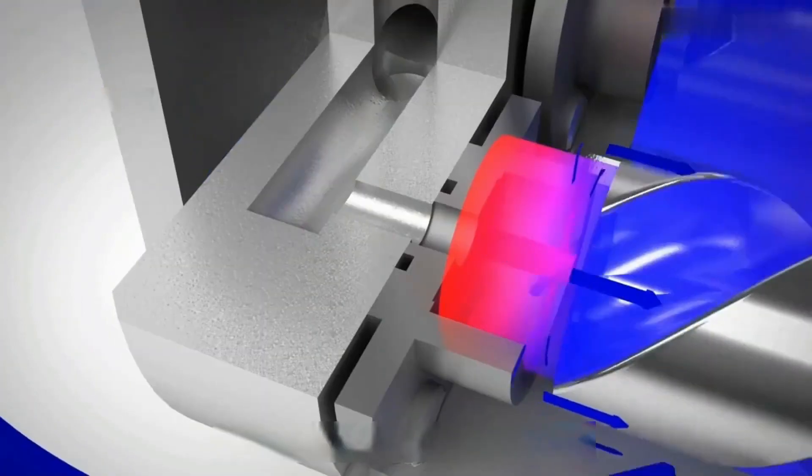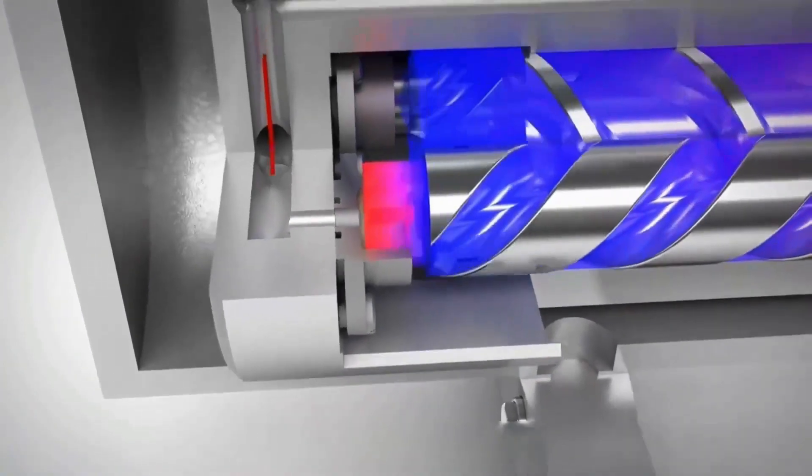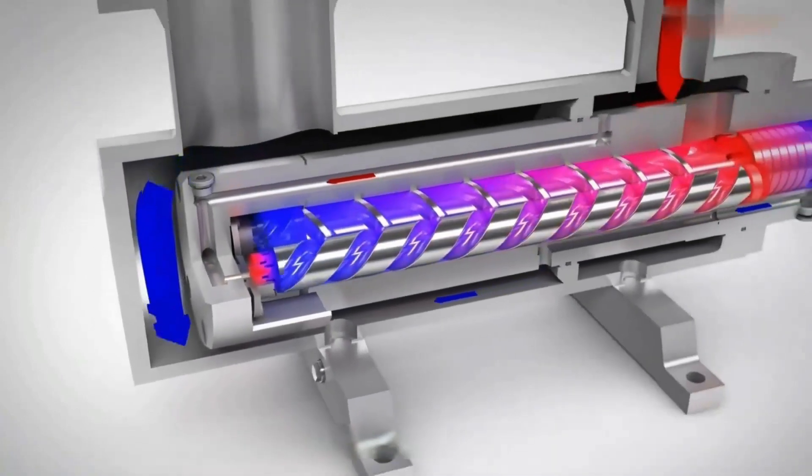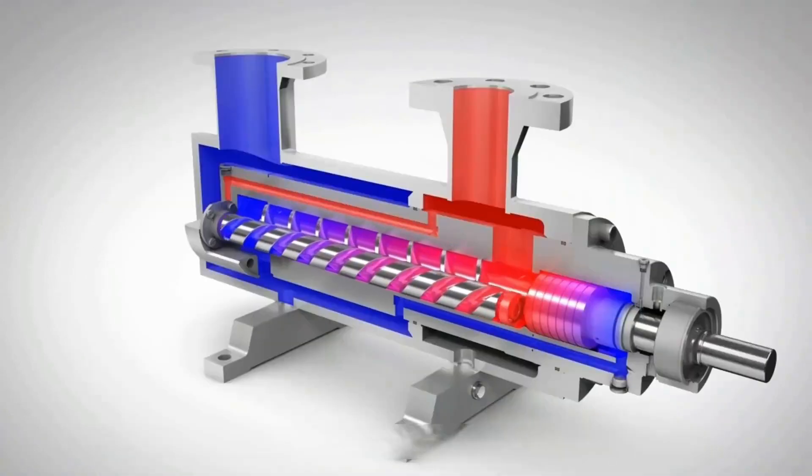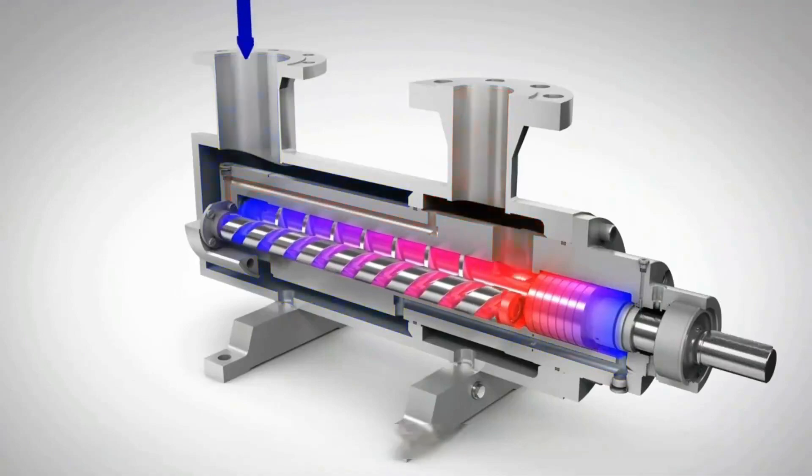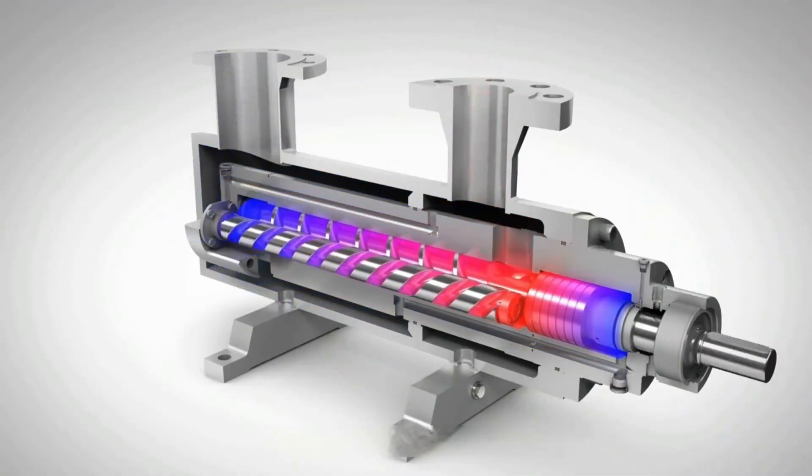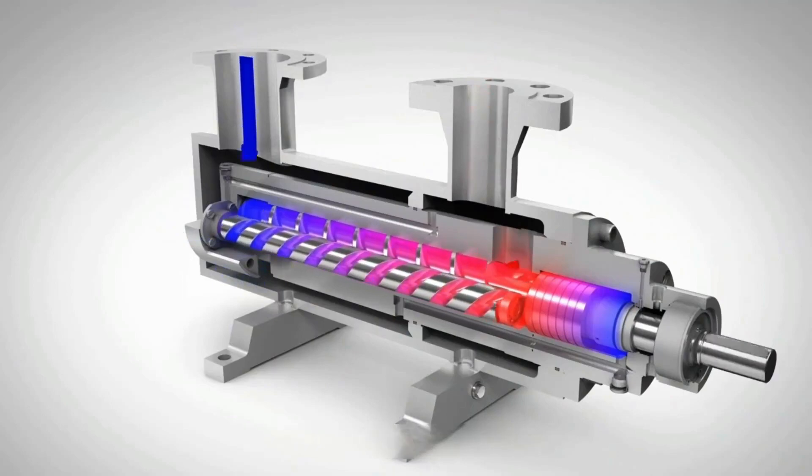The fluid is sucked into the sealed space between the threads and the pump casing and moves with the rotation of the screws. The volume of the fluid is gradually compressed, the pressure increases, and finally it is discharged from the outlet valve.